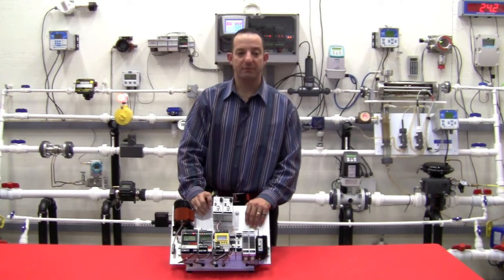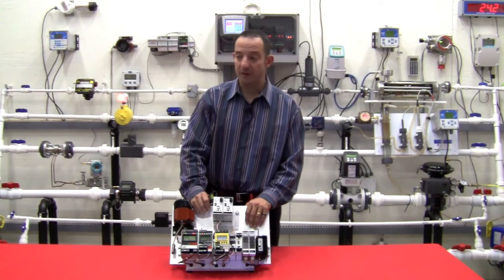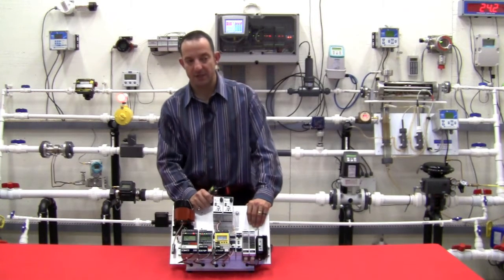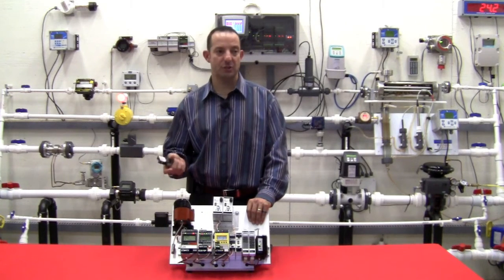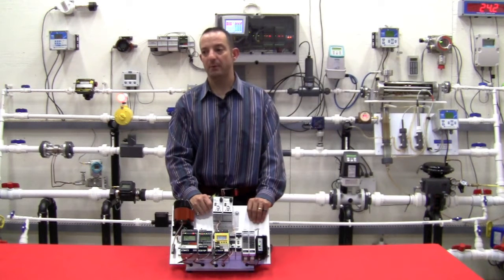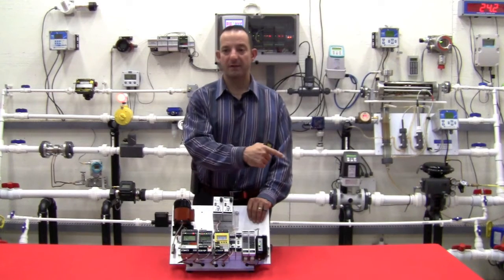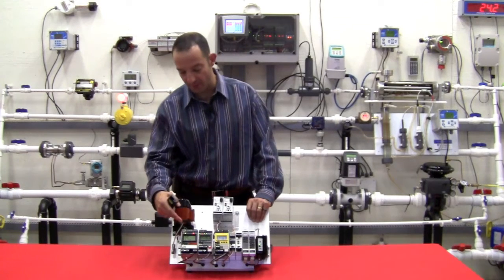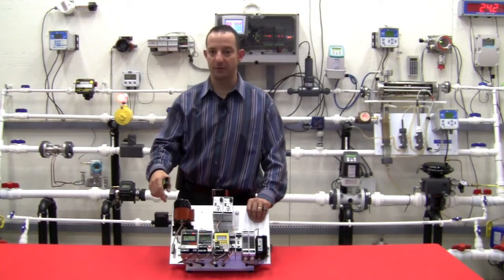Applications for this type of device are valve positioners. If a customer is using a HART digital valve positioner, a module such as the HIM allows you to extract the true valve position feedback signal in that HART data stream, so that the customer not only knows what the analog signal telling the valve where to go is, but the control system also now knows where the valve actually is, because the true valve position is in that digital data stream.